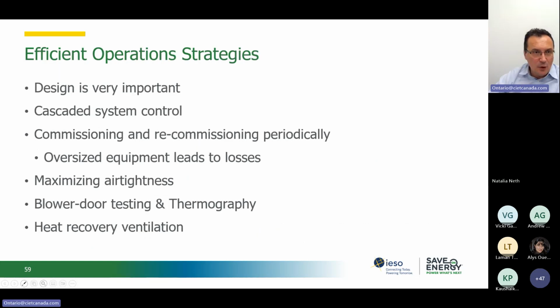The type of operating strategies that we can also consider, definitely look at the design, using proper modeling tools to right size the equipment, selecting the option that will look at the operating aspect, not just the first cost. Cascade control, I mentioned, is a way to prioritize which equipment will run more based on the equipment efficiency. As equipment becomes more and more efficient, it does require that retuning, recommissioning periodically, and we'll see this as part of our buildings as well.